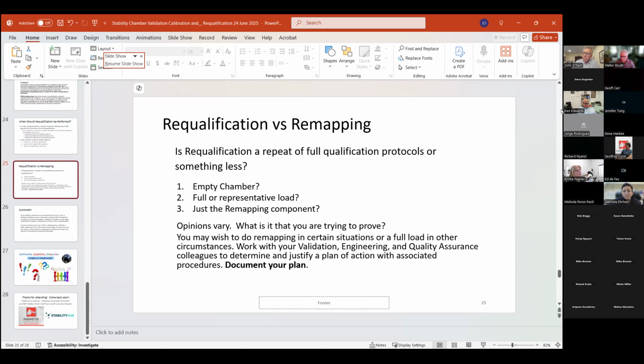I did see a question in here where somebody has asked whether, if they have multiple probes in the chamber, it's still necessary to do remapping. I would say it's pretty unusual to have multiple probes in a chamber. The chambers I'm familiar with only have one continuous recording probe in them, which is why we remap annually. If, on the other hand, you do have multiple probes in the chamber in the same locations as were used for the qualification, I would say that you don't have to remap because you're continuously remapping all the time anyway. But I think it would be an unusual situation to have that sort of configuration.